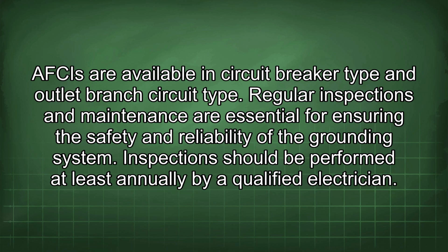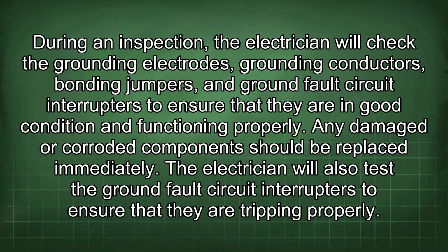Regular inspections and maintenance are essential for ensuring the safety and reliability of the grounding system. Inspection should be performed at least annually by a qualified electrician. During an inspection, the electrician will check the grounding electrodes, grounding conductors, bonding jumpers, and ground fault circuit interrupters to ensure that they are in good condition and functioning properly. Any damaged or corroded component should be replaced immediately. The electrician will also test the ground fault circuit interrupters to ensure that they are tripping properly.